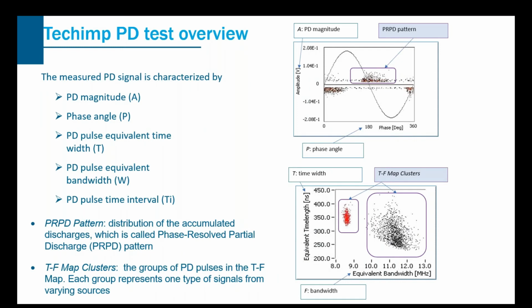Before we talk about signal separation, we need to know what signal we're looking at. What parameters do we save for the PD signals that we acquire? In most PD testing systems, the acquired parameters are the PD magnitude, such as Qmax or Qmean, and the phase angle. These are the two typical parameters that almost all PD testing systems acquire. With Techimp PD testing technology, we have three additional parameters that we save all the time, the first of which is the equivalent time width, or equivalent pulse width.